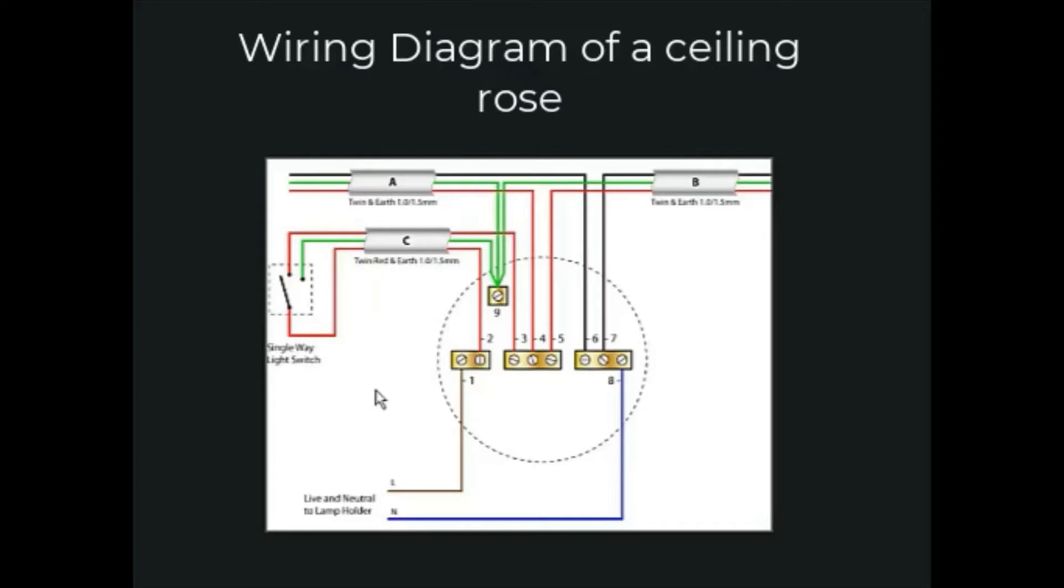In the diagram three terminals are shown. The blue wire goes to the right neutral terminal, the red wires go to the middle live terminal, and the brown live wire from the light pendant goes to the left terminal. The diagram shows a loop in loop out configuration.